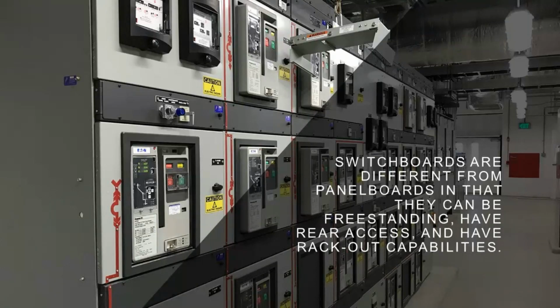That rear access is important for bracing. There's all kinds of stuff. And I don't know how many of you guys have worked in an area where there's a big switchboard or medium voltage gear. If you see the red arrows on this stuff, it actually shows you which way the bus is arranged all the way around and which section feeds the other section. I don't know if you guys have ever seen that, but that's incredibly helpful, especially when you're first taking a look at it and you're not sure what's going on. As an inspector, when I walk into something like this and I see all this gear, it's overwhelming until you start taking it piece by piece, and then you start saying, okay, well, this breaker comes down here and feeds over, and I can follow the red line. All right, this one feeds this one feeds this. And it makes it pretty straightforward.